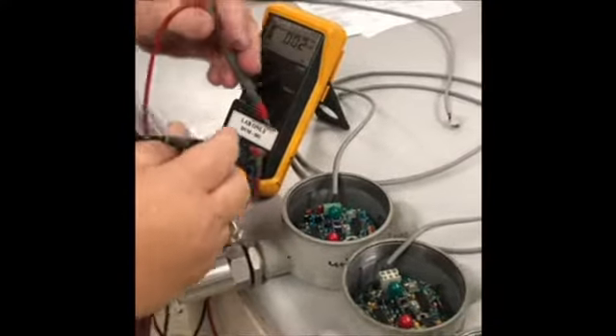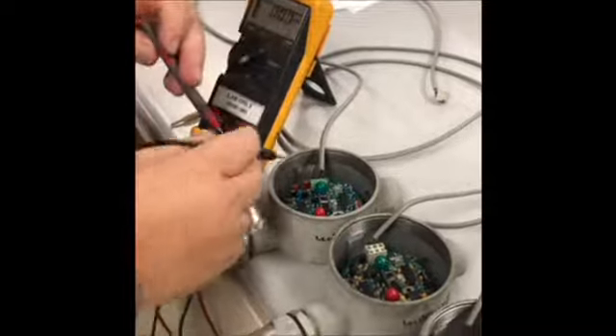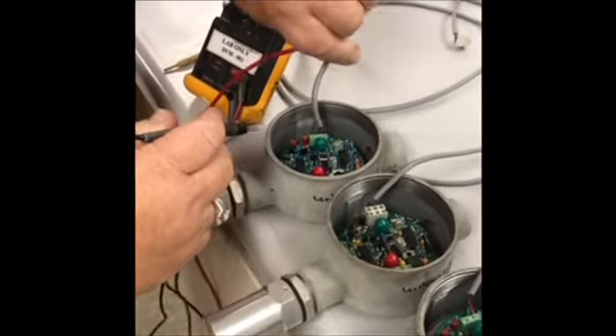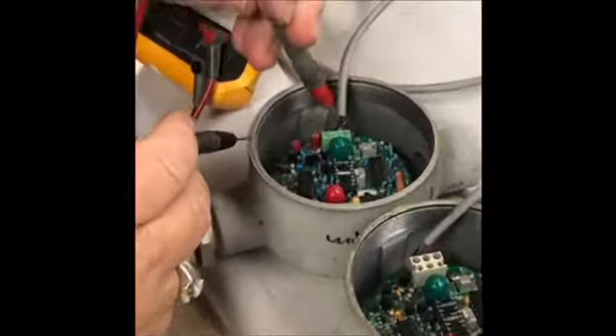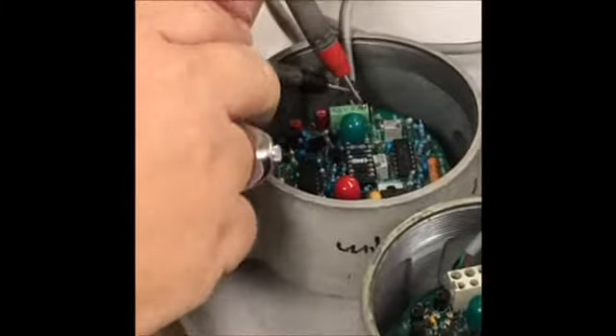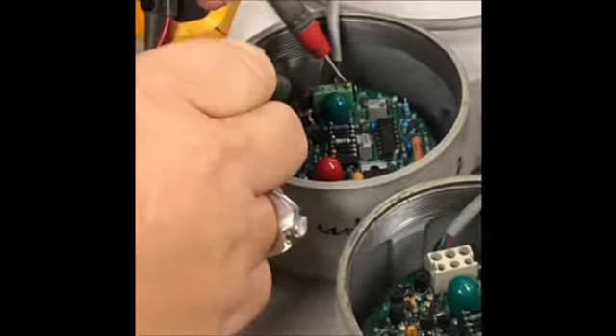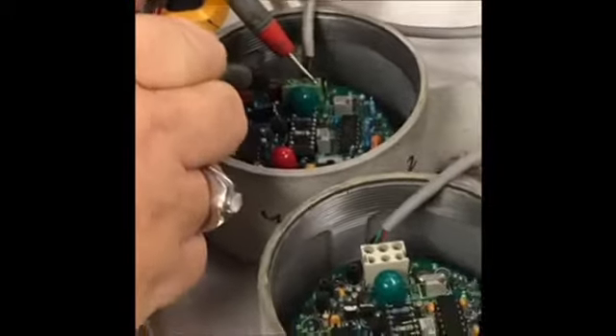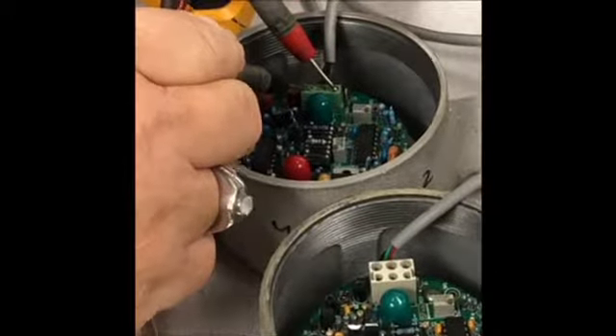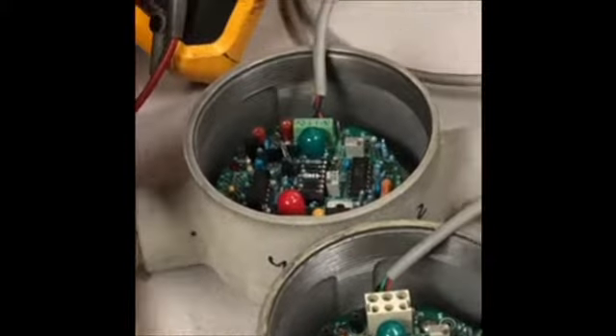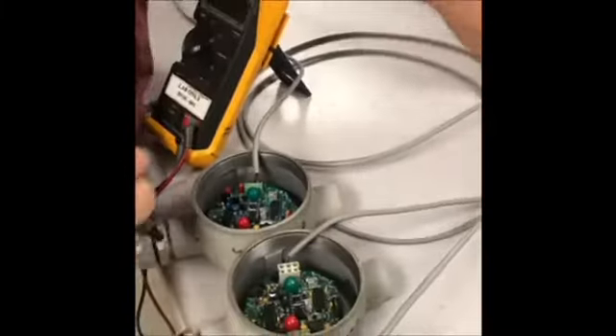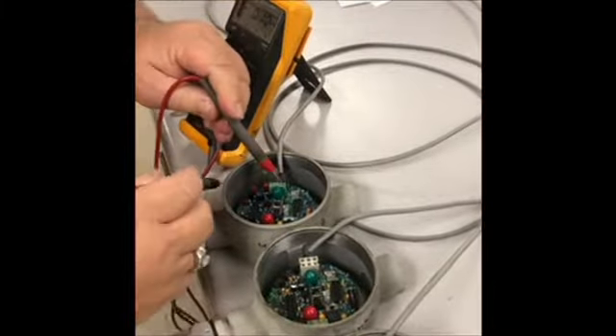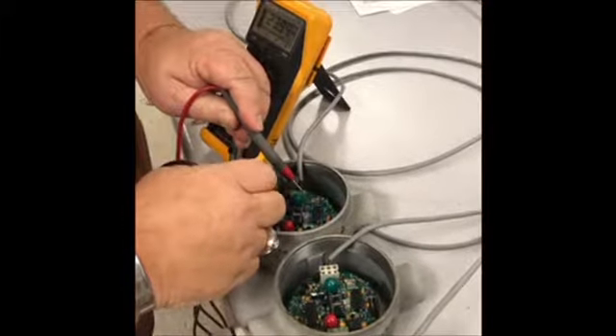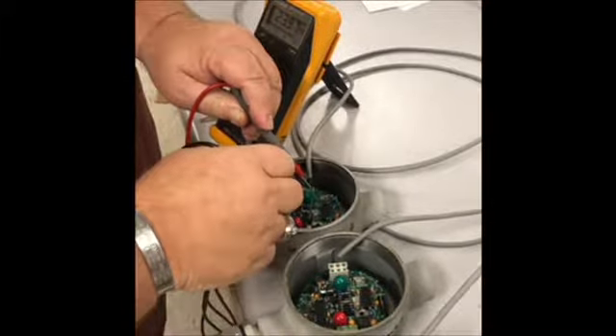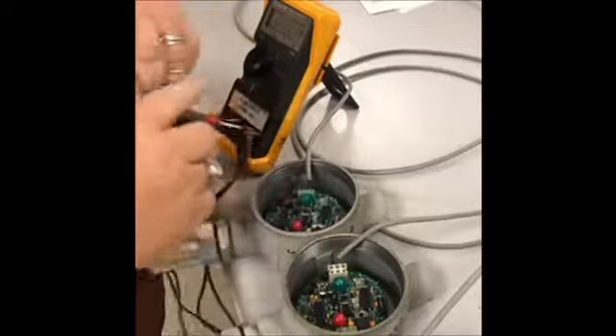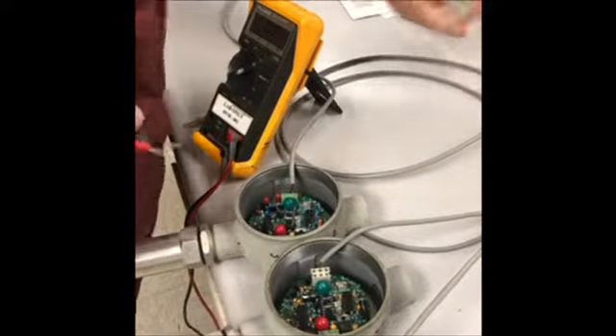You can also make sure that it's disconnected by measuring it at the terminal block. This is the terminal block coming from the power supply. You put the red probe on the red wire, and the black one on the black one. Those are the two outside ones, pin 1 and 3. You'll see that there's no voltage there. If I plug it back in, when it's plugged in, you'll see there's 24 volts. That's normal. 24 volts is what it runs on. So we're going to remove the power again.